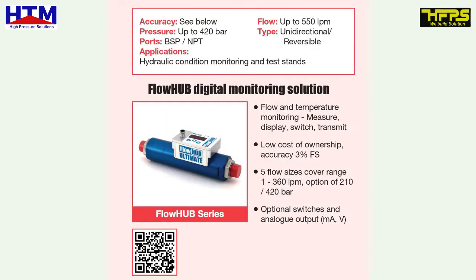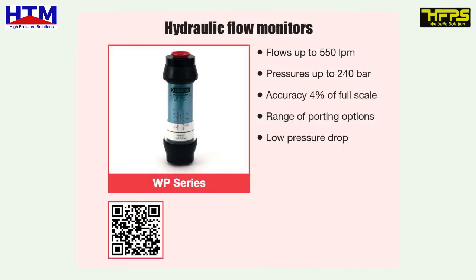Flow hub digital monitoring solution for flow and temperature to measure, display, switch and transmit. Accuracy 3% F.S. 5 flow sizes cover 1 to 360 lpm, pressure either 210 or 420 bar. Optional switches and analog output, milliamps, voltage. Ideal for lubrication systems. Hydraulic flow monitors. Flow rate maximum 550 lpm. Pressures up to 240 bar. Accuracy 4% fs. Range of porting options allows very low pressure drop.